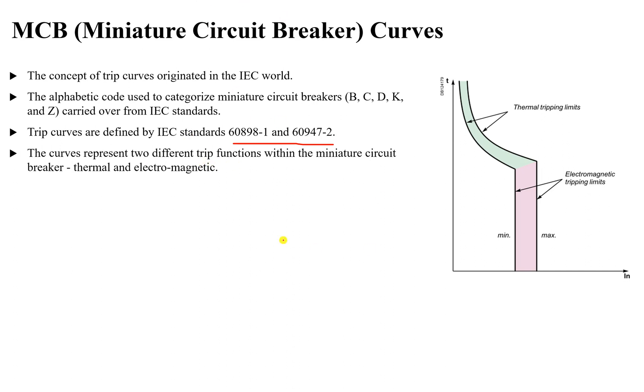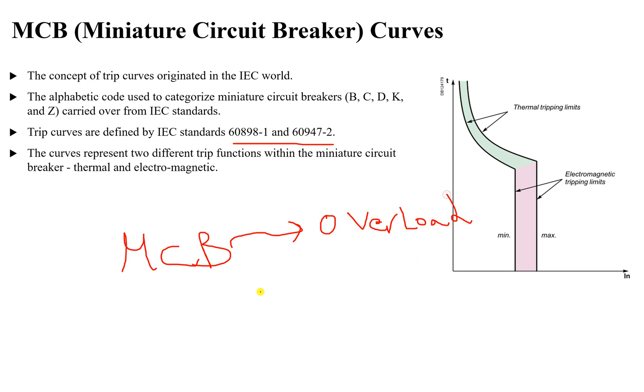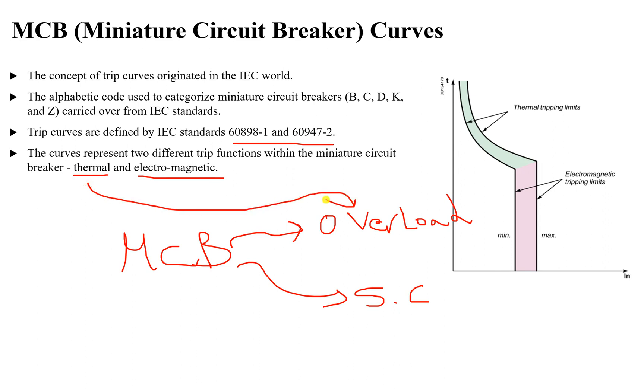These curves — B, C, D, K, and Z — represent curves with two trip functions. The miniature circuit breaker serves two functions: number one, protection against overload conditions, and number two, protection against short circuit. These two functions are defined by two mechanisms inside the miniature circuit breaker: a thermal mechanism and an electromagnetic mechanism. The thermal mechanism is associated with overload conditions, and the electromagnetic mechanism is associated with short circuit conditions.